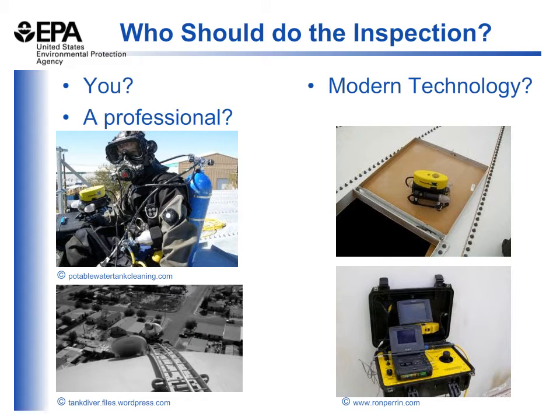So who should conduct a water tank inspection? Should it be you as the operator? Should it be the manager or someone else at your utility? Should you hire a professional? Well, in the case of an elevated tank, an inspection could be both dangerous and specialized, and it may be best to employ a professional or qualified firm to do a tank inspection. This professional will typically submit a report to you, the system owner, with the conditions of some of the things that they have inspected and suggestions on repairs that you may want to make.